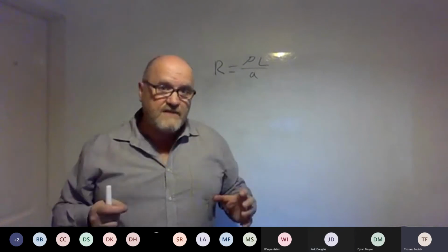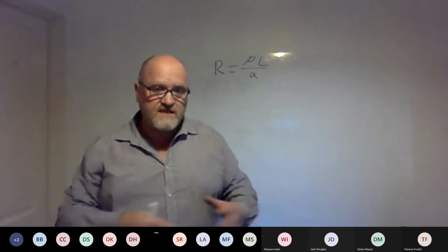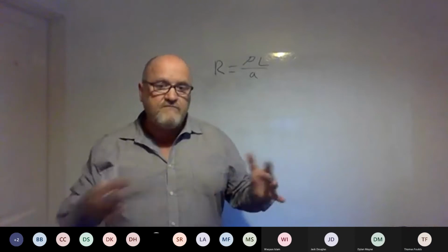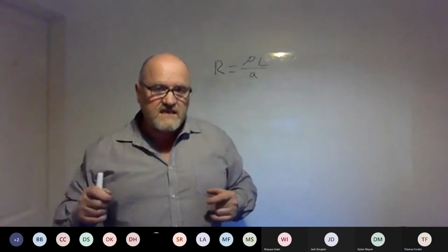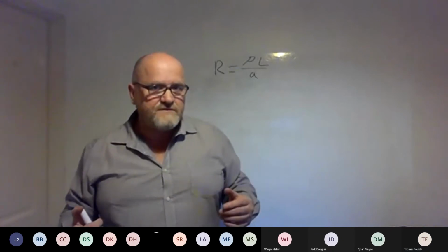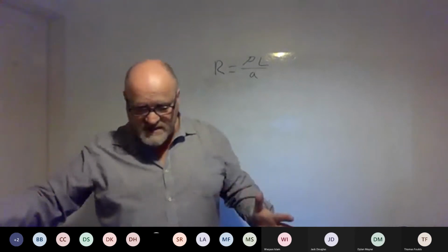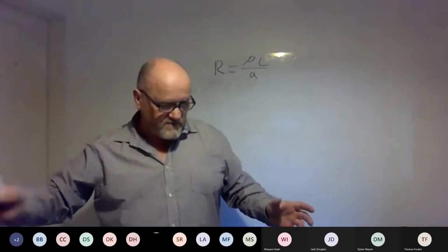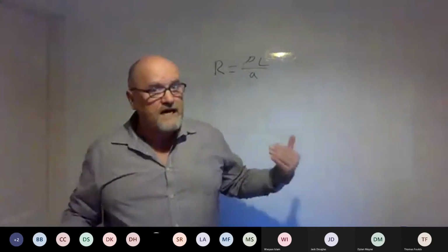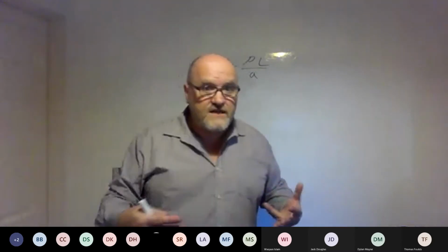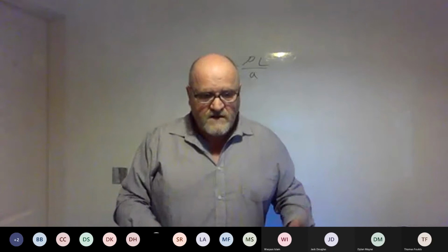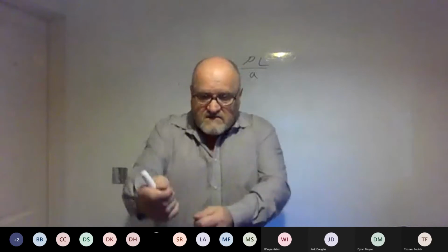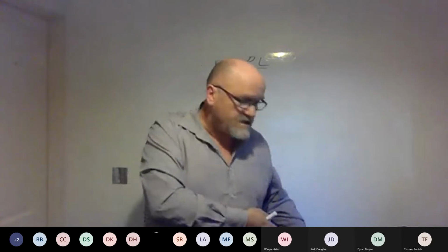Yeah, so when you install cables, and you've got a drawing that says you've got to put 35 metres of 10 mil cable in, when you test it, you know what your expected readings are going to be. Because you look at a drawing, I've got 25 metres of this 4 mil cable. When I install that, I know what the readings are because I've just worked it out on paper, because I'm now an electrician doing design as well, which you will do. And when I go and build it and test it, the readings I've got are what I've worked them out to be.